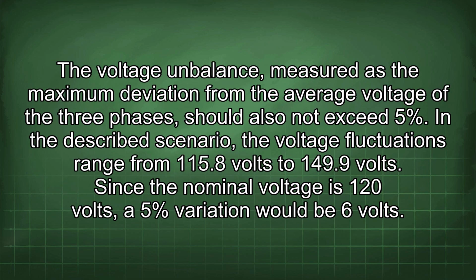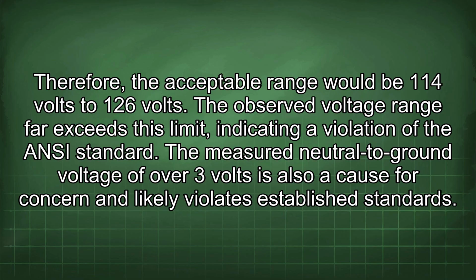The voltage imbalance, measured as the maximum deviation from the average voltage of the three phases, should also not exceed 5%. In the described scenario, the voltage fluctuations range from 115.8 volts to 149.9 volts. Since the nominal voltage is 120 volts, a 5% variation would be 6 volts. Therefore, the acceptable range would be 114 volts to 126 volts. The observed voltage range far exceeds this limit, indicating a violation of the ANSI standard.